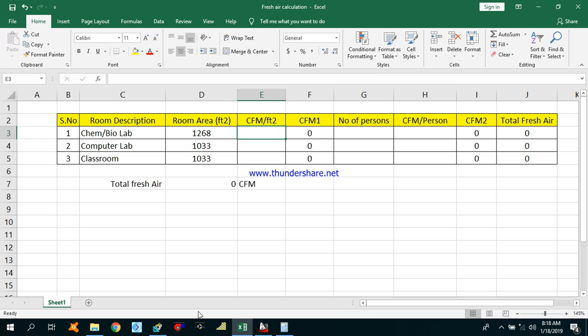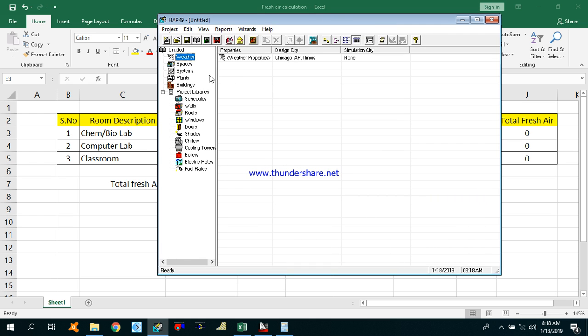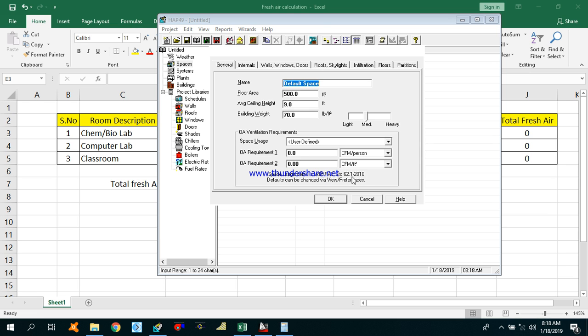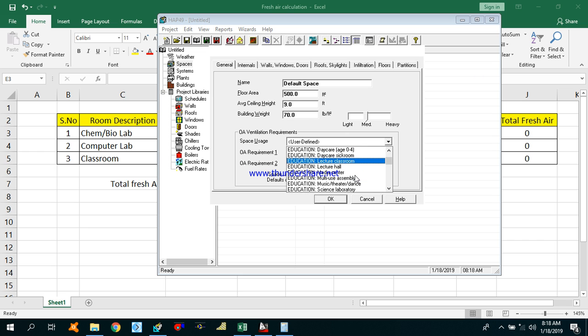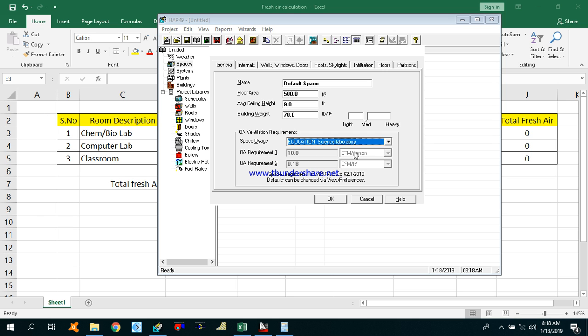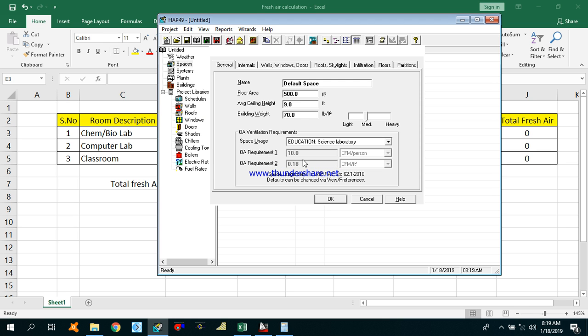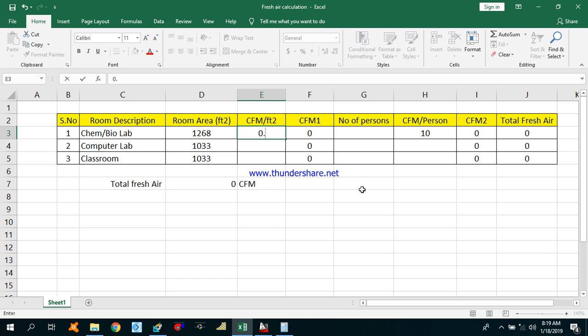For the CFM per square feet values, I have opened the HAP software. Going to Spaces and then New Default Space, you can select the ventilation requirement as per ASHRAE Standard 62.1. For the science lab — chemistry and bio lab — under Education, we find the CFM per person is 10 and the CFM per square feet required for a science chemistry lab is 0.18.